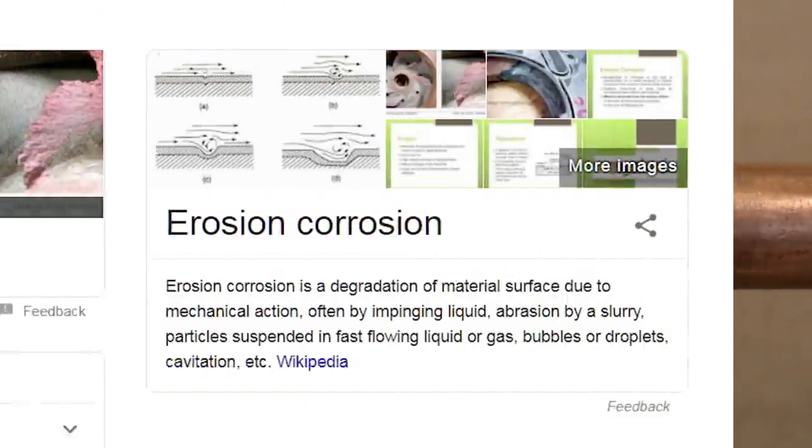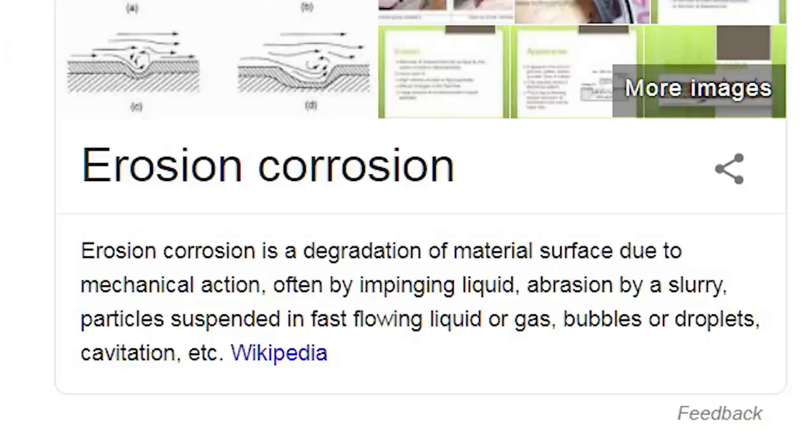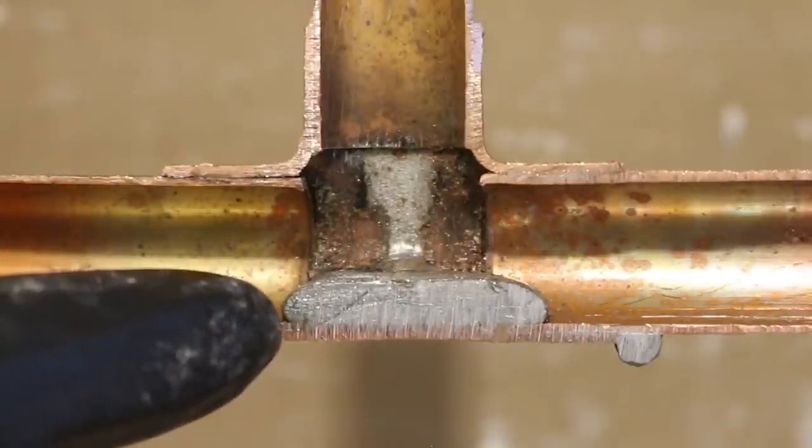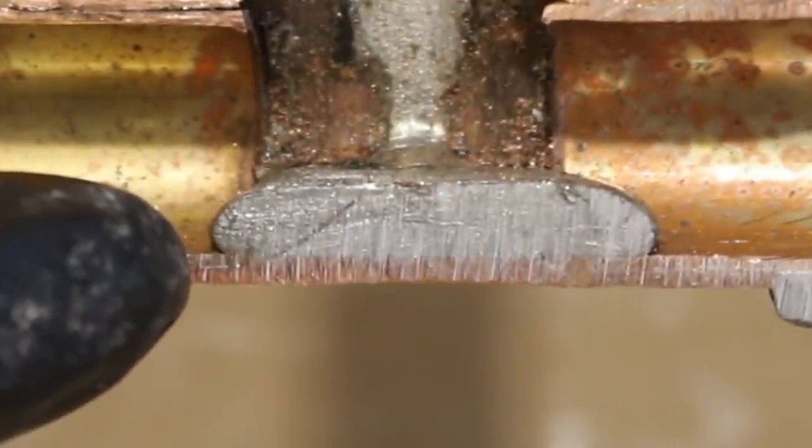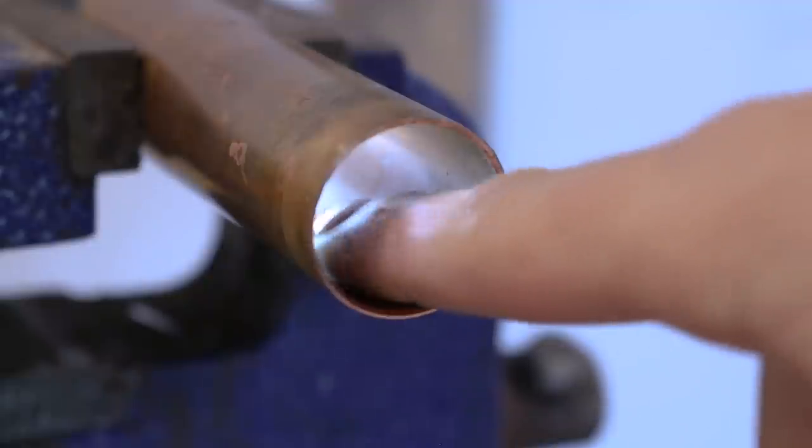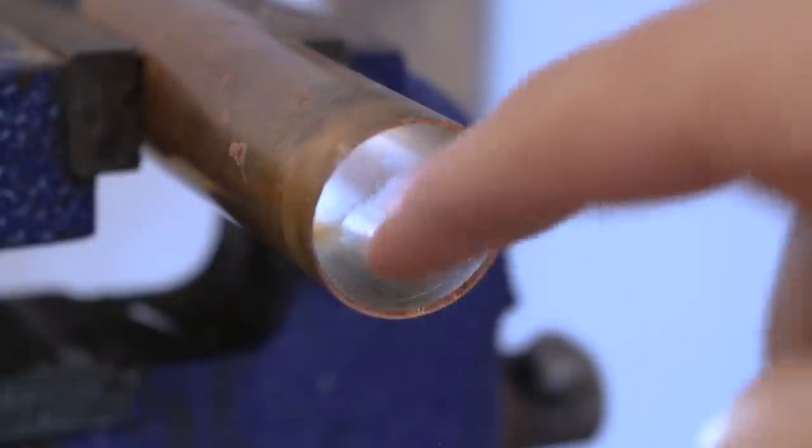It might seem drastic, but according to the CDA or Copper Development Association, this is the most common mistake to make which causes pinholes. Something else that causes turbulence is if you apply too much solder. It accumulates inside the fitting and creates a similar problem. So to avoid this phenomenon, it's important that the inside of the pipe remains at its full bore.